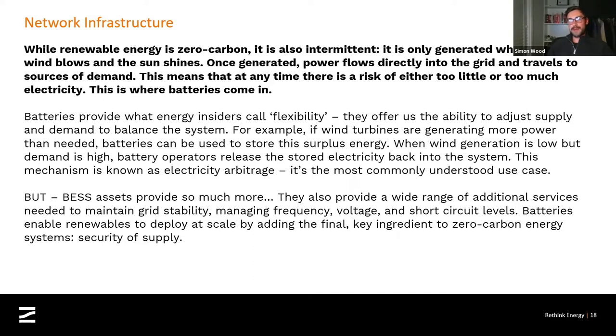But where batteries really provide the most benefit is more around stability management. Some of you may be aware of the concept of grid frequency. Our electricity system anywhere in the UK is generally operating at around 50 hertz. And if we go above or below that, we start to get an unstable network. And if we go too far above or too far below that 50 hertz band, the system will start to protect itself and start tripping out. So for National Grid, it is absolutely imperative that the electricity network maintains around that 50 hertz frequency level. Batteries are brilliant because they can track frequency and respond to very small deviations in grid frequency by importing or exporting active power. And in doing that, they can help to stabilize the frequency of the network.